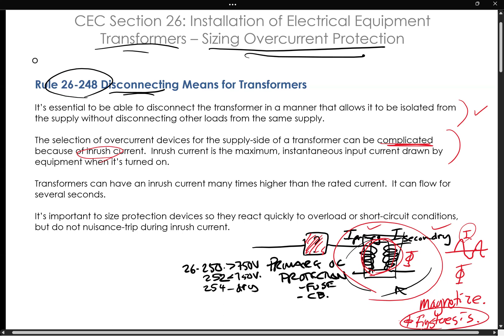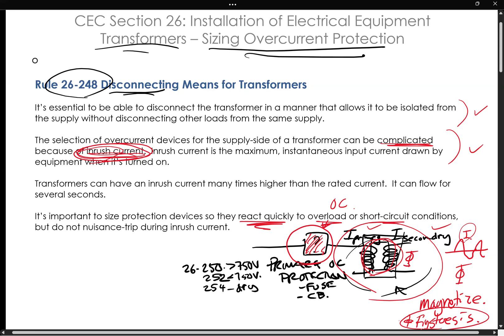From practical means, as a person taking your electrical exam, you need to know what is this overcurrent device so that you can let this inrush current happen — because it's going to happen. You don't want to nuisance trip this overcurrent device, but you also need to protect the circuit like an overcurrent protection device should. So this is a fine line, and that's why the upcoming sections — Rule 26-250, 252, and 254 — are a little bit complicated. It's important to size those protective devices so that they react quickly to overload or short circuit conditions, but not to nuisance trip during the inrush current.